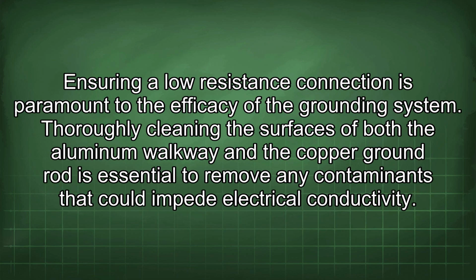Ensuring a low resistance connection is paramount to the efficacy of the grounding system. Thoroughly cleaning the surfaces of both the aluminum walkway and the copper ground rod is essential to remove any contaminants that could impede electrical conductivity.